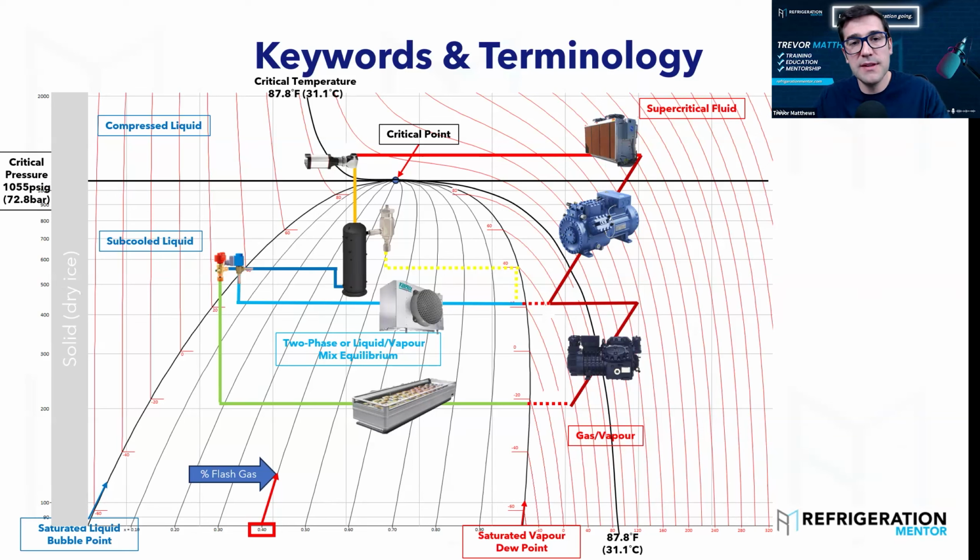I think that's been the game changer for me from learning design and engineering on CO2 systems: plotting all these numbers. When you can plot all these numbers where they're at, you can understand how to troubleshoot a system way faster. I've seen technicians come into my supermarket and CO2 programs and start plotting the numbers for voltage, pressures, and temperatures. And they're like, this makes so much more sense. This is why this three-way ball valve is switching. It's not to do with anything but temperatures or pressures or voltages, and understanding how to plot it.